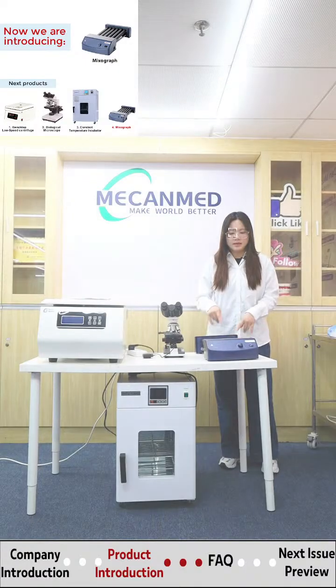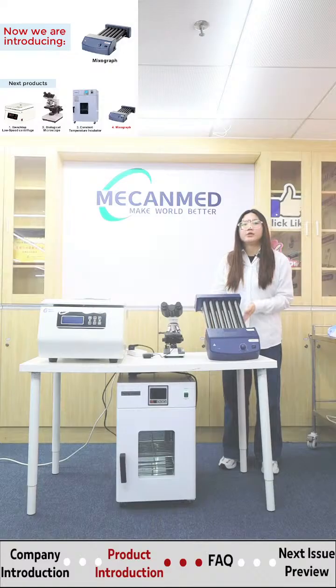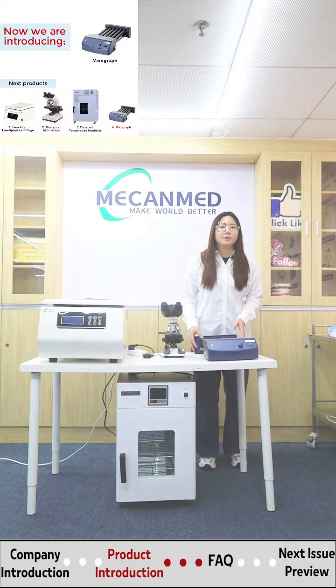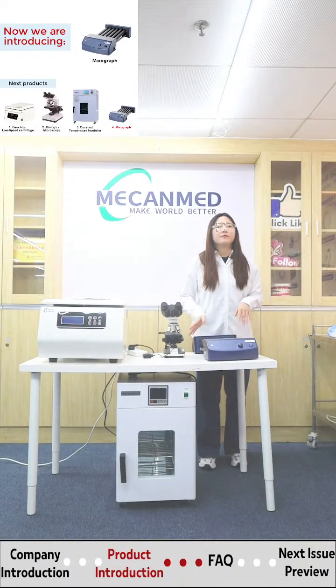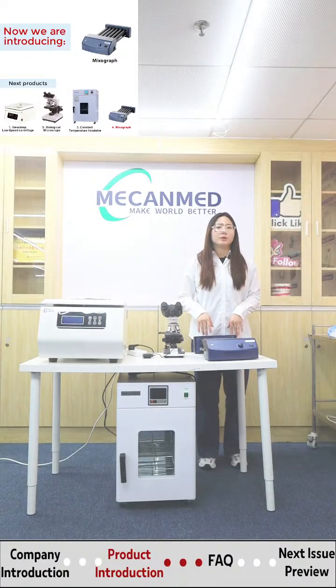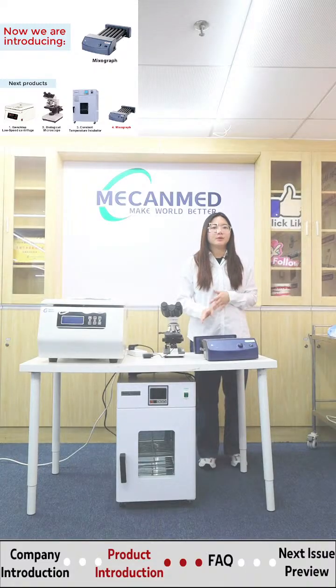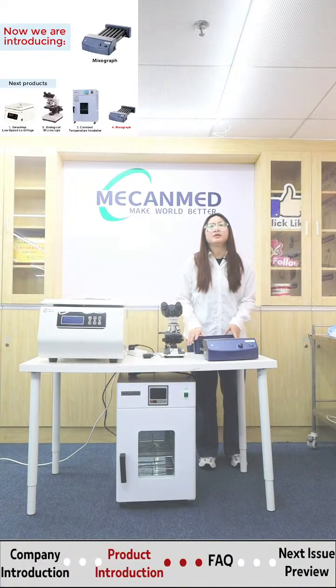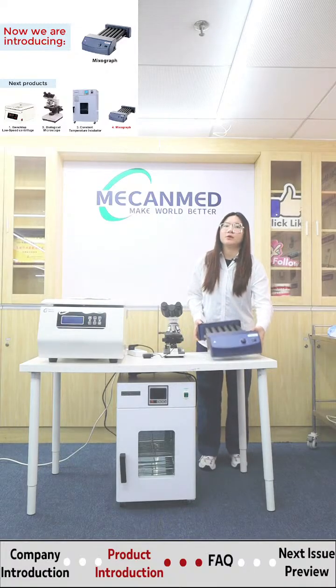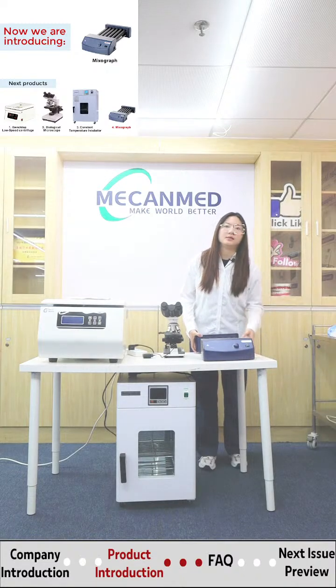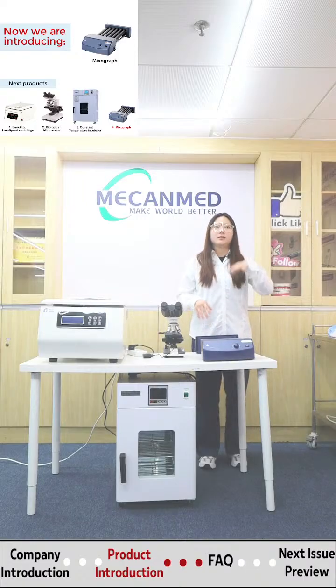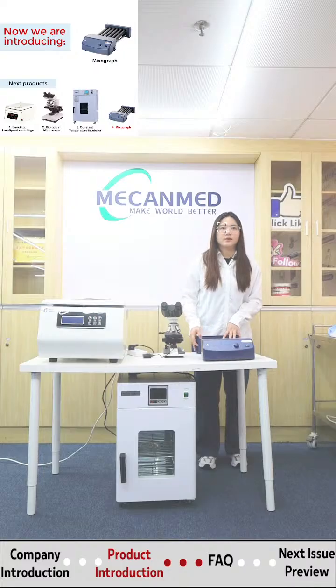The mixer is equipped with 6 rollers. Each roller is 280 millimeters in length, so they provide ample contact with the sample. Additionally, thanks to its continuous operation mode and large diameter rollers, it enables exceptionally gentle mixing. And finally, the compact design. With dimensions of 450 by 260 by 120 millimeters and a weight of only 4.5 kilograms, it occupies minimum lab space and is easy to move when necessary. Okay, let's take a quick look at how effortless this really is.